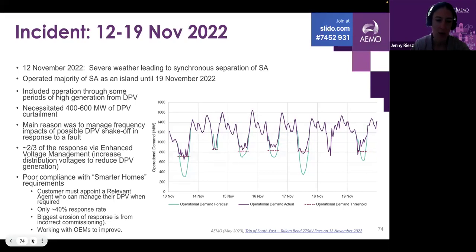In parallel, we've attempted to put in place a smarter homes requirement, where customers appoint a relevant agent who manages their PV when required. That's been put in place, but unfortunately we're only seeing 40% compliance. Again, compliance is the problem. The biggest erosion of response comes from systems not being set up properly at commissioning. So SA Power Networks is working with original equipment manufacturers to improve that response rate.